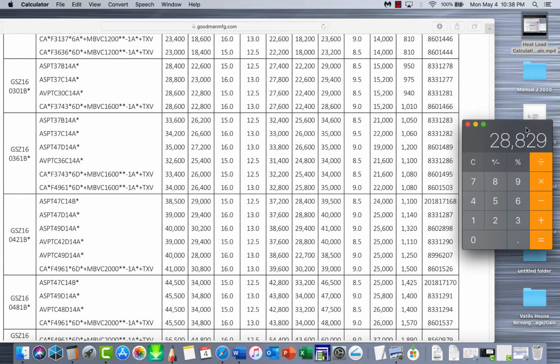So with a number like 28,800, you could round that up and just say 29,000. So any units like this, if you're looking at the sensible on them, this unit is not going to meet our demand. It will make the demand for a vast majority of the time, like 80%. But once it gets past 93 degrees, as we base this calculation on, this unit will not make it. It will not keep that house cool. So we have to have something that is right near this number.